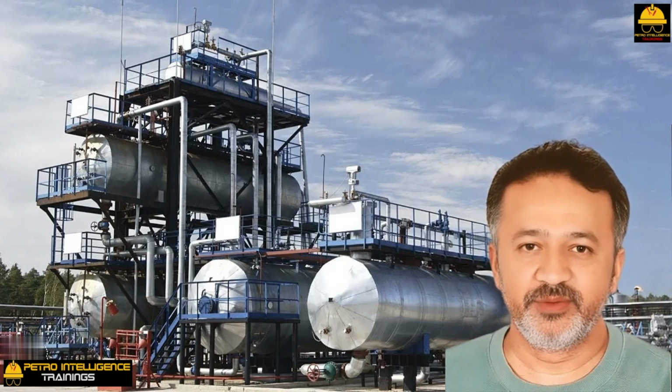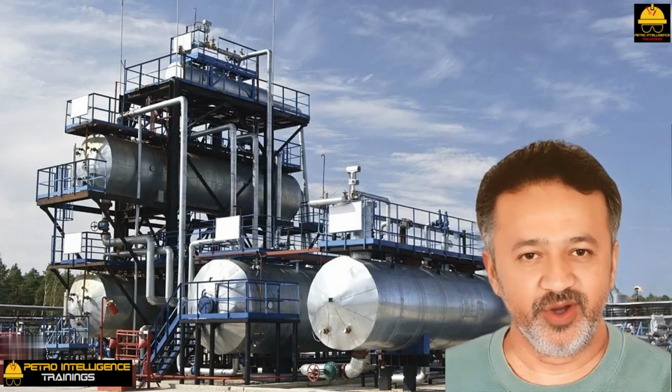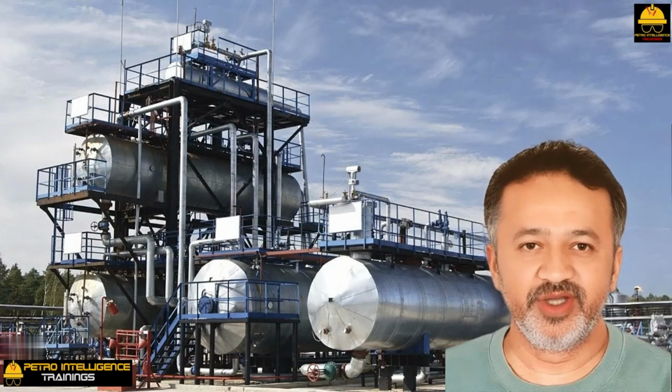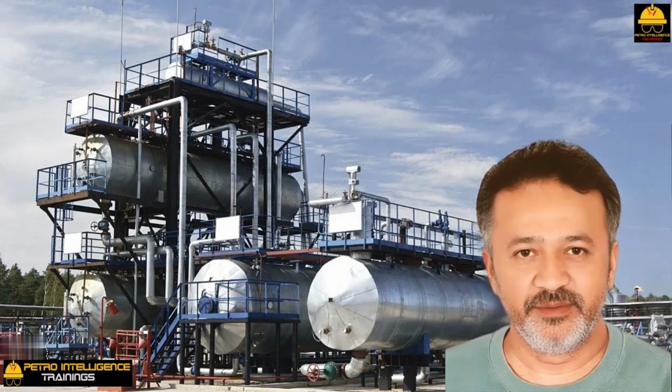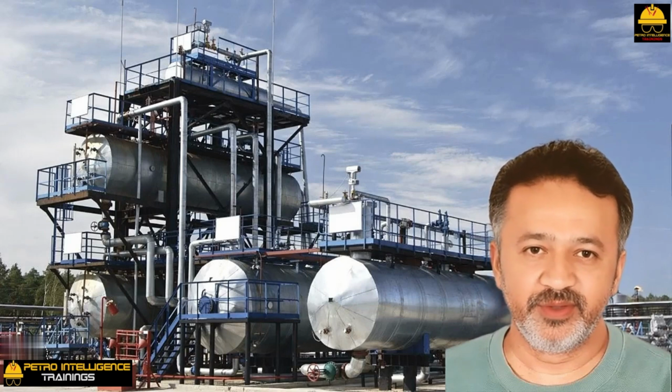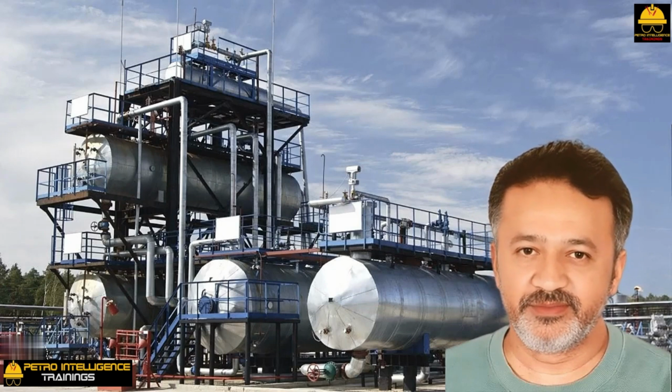Most electricity is produced from steam by use of a steam-powered generator. Typically, it takes 3 BTU of steam to generate 1 BTU of electricity. That is why it is best to use the steam directly, at least for heating purposes, if the distance between the boiler house and the consumer is small.